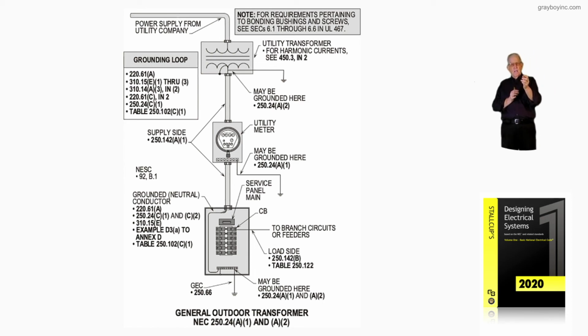250.24(C)(1) and (C)(2) is dealing with the transformer grounding and the service equipment starting it. 310.15(E) deals with how we'd use the neutral in the system. Then examples of what I'm telling you, you can find in Annex D in the back of the NEC, starting with Annex D3(A), Annex D as in dog. And then again, you have to size the effective ground fault path by table 250.102(C)(1). Now, this covers the most important things, but notice supply side grounding is the arrows pointing to the line side of that meter and to the load side of the meter down to the protected device.